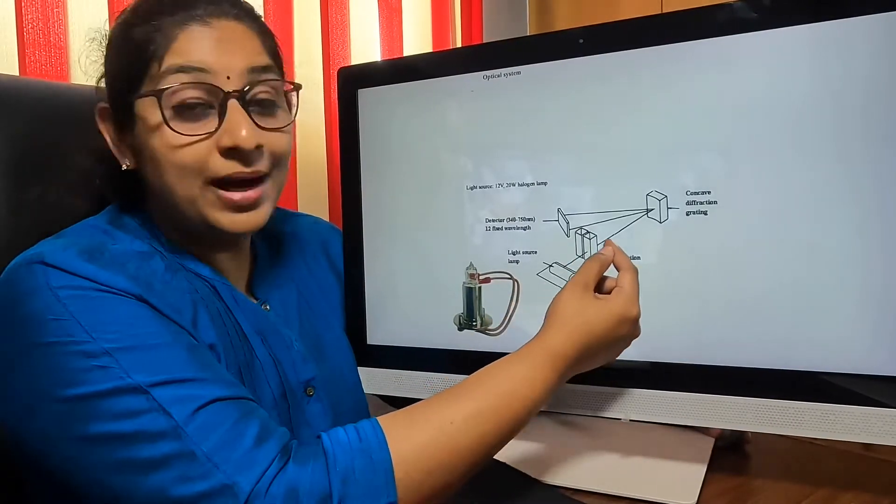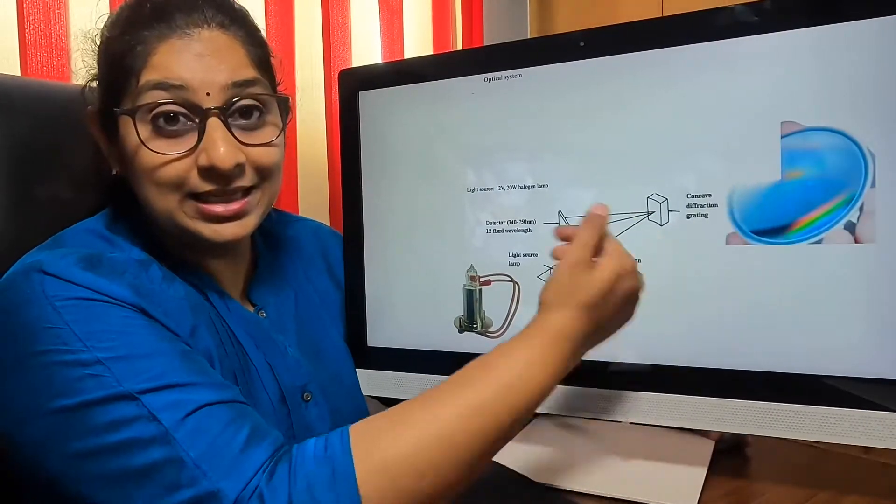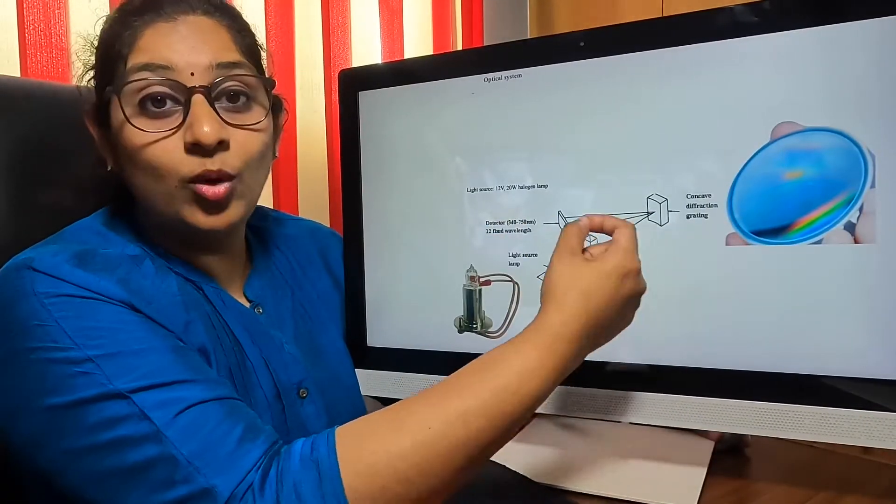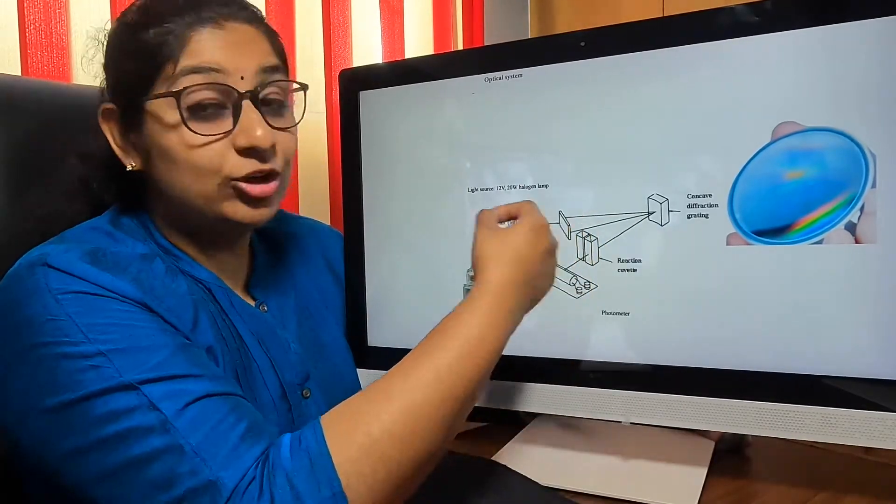From this, the light passes through the reaction cuvette into the concave diffraction grating system, and from that, whatever particular wavelength we have, the light is going to go into the detectors.